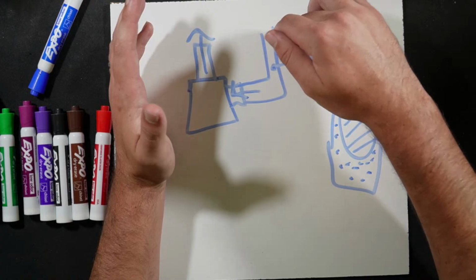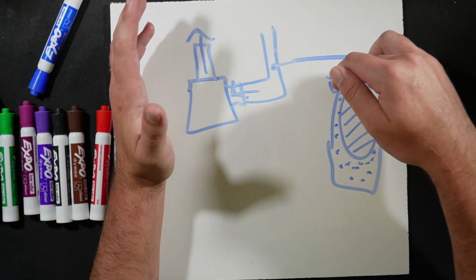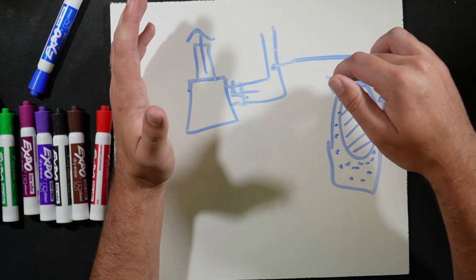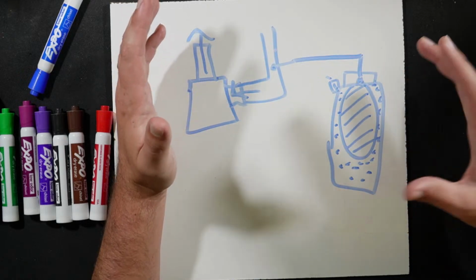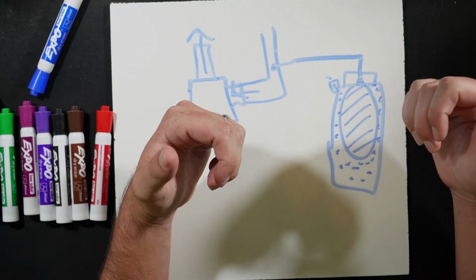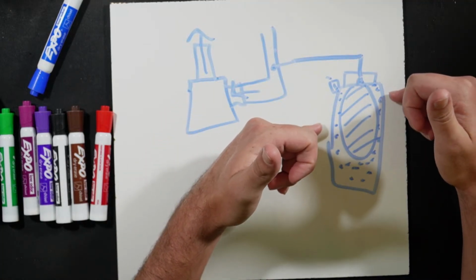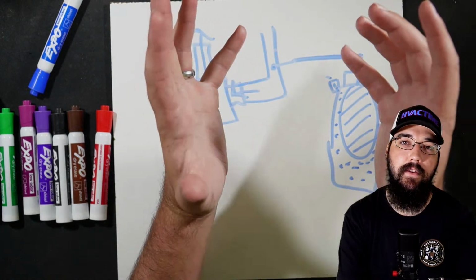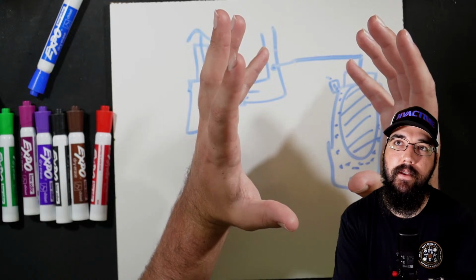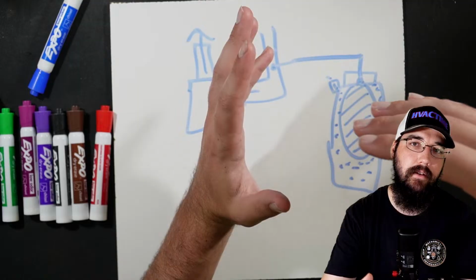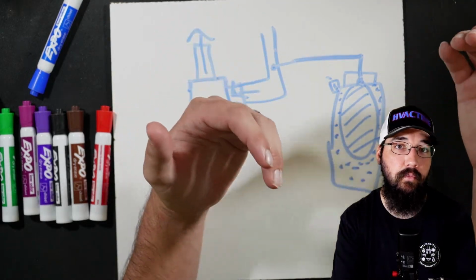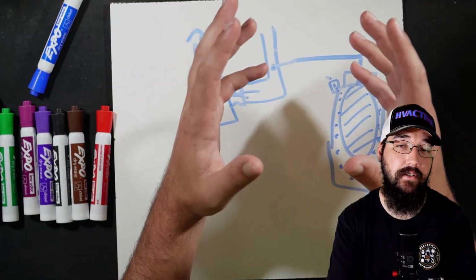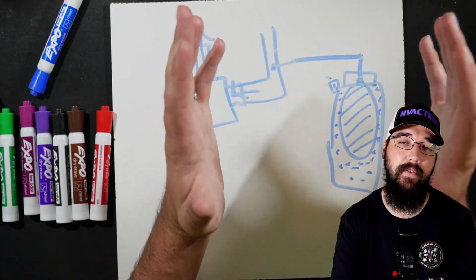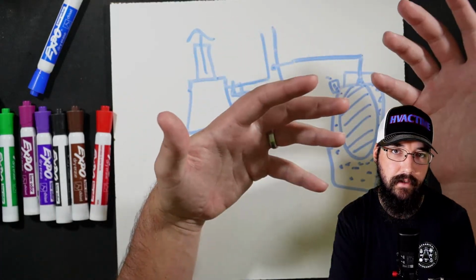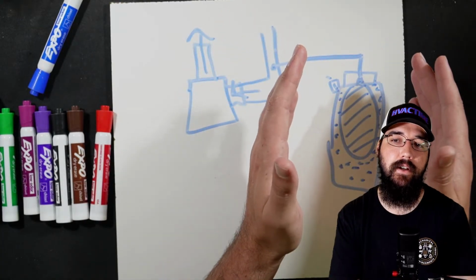So with the loop at operating temperatures, you will use just a regular air chuck gauge, and you will set this tank pressure to that. They'll come preset. I've seen them at 12 psi or something, which is pretty common for these to come from the factory. If your tank was at the top of the loop and you're running a normal loop, at the very, very top of the loop, your return line that goes back to your pumps, I would expect that to be roughly 10 to 12 psi, typically. A lot of times that is the preferred place for it to go, so that default pressure straight out of the box would be fine.